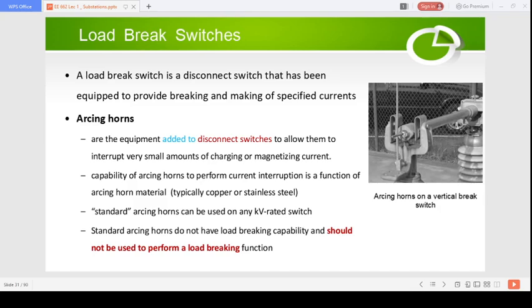Okay, so you can see here the arcing horns on a vertical break switch. The capability of the arcing horn to perform a current interruption is a function of the arcing horn material. So the ability to interrupt the currents depends on the material of the arcing horn. You can see it in here. Typically it's made out of copper or stainless steel.